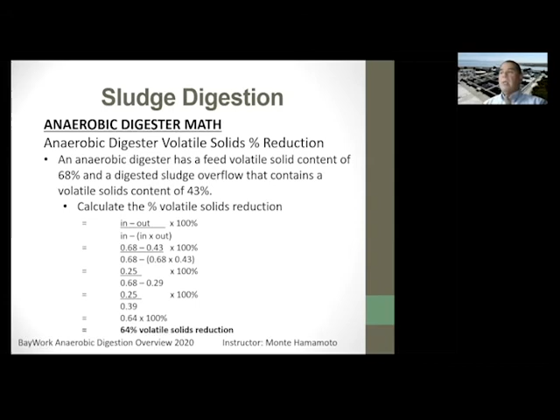When you plug these numbers in, you'll come out with 64% volatile solids reduction. Looking back at our design criteria, I believe we are between 40 and 60%. So we're actually working a little above design criteria, which is a good thing. We can push our digesters a little more than the engineers thought we could. This is just a way to check your digester against design criteria and see if you're operating it properly.